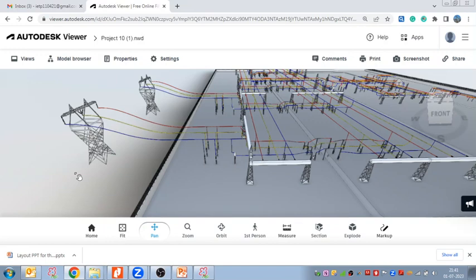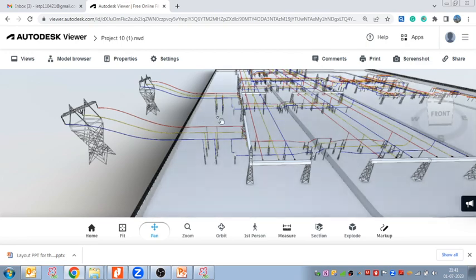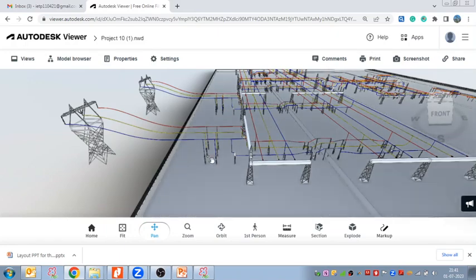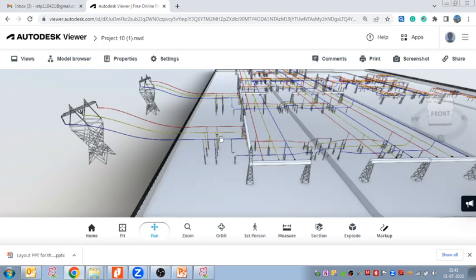So when you are making the layout drawing, in that case you have to make a circle here on the line side equipment. You have to make a cloud mark on the surge arrestor, CVT, and the wave trap, and you have to write a note in your drawing that the location of surge arrestor, CVT, and wave trap shall be decided based on the dead end tower location. This you have to put on hold.